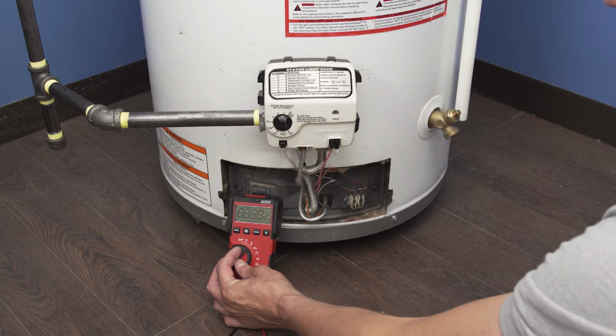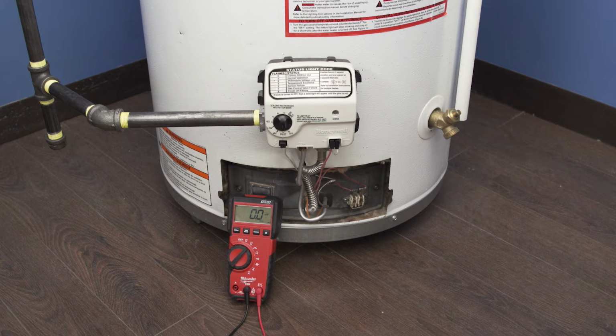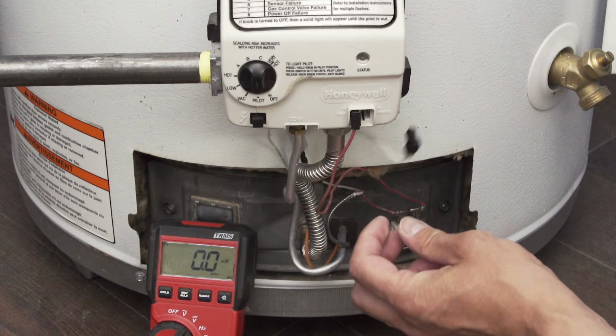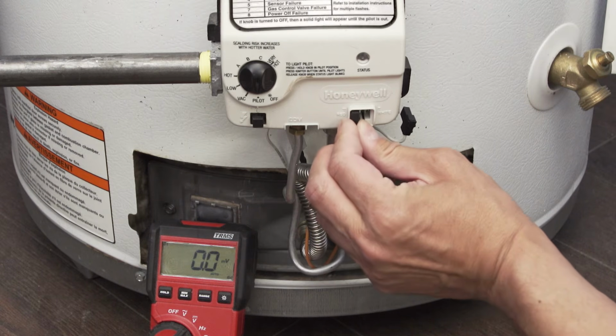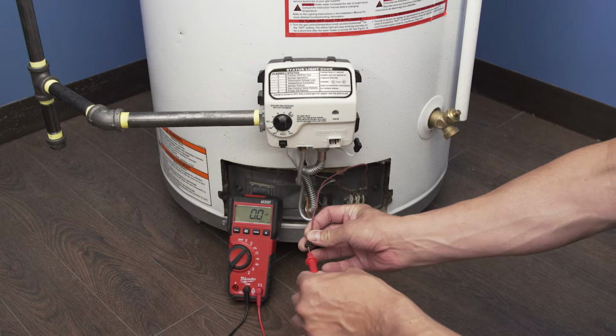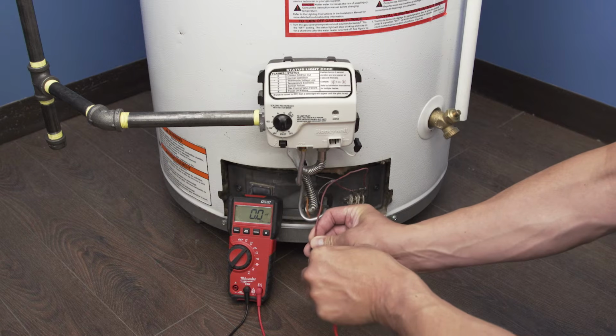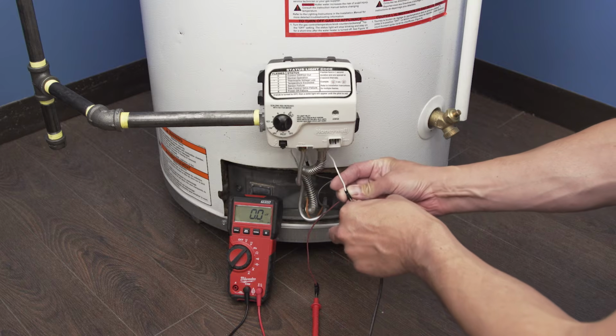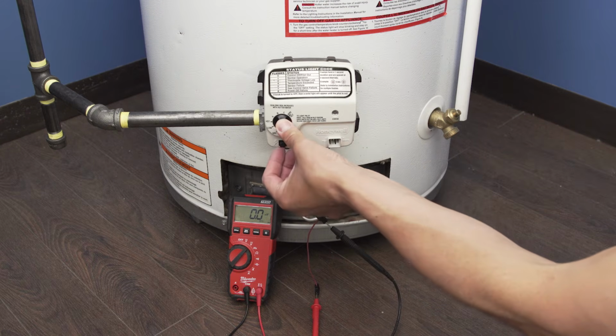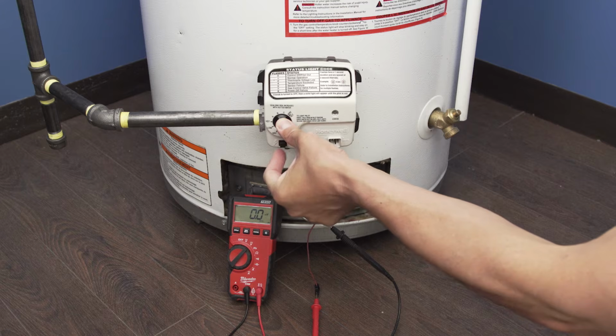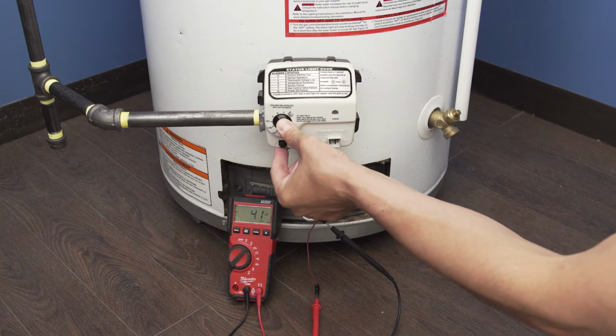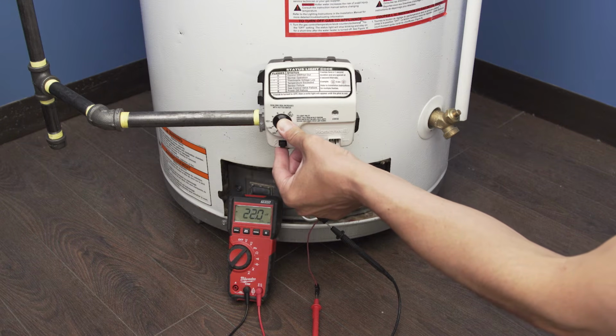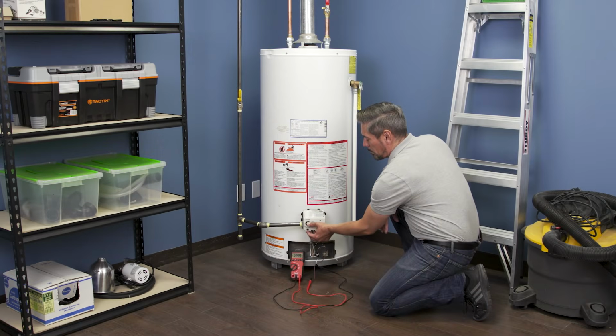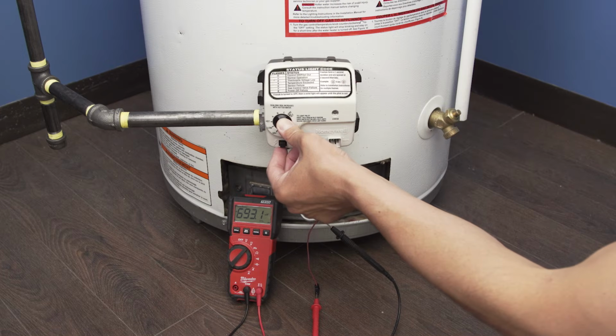First, set the multimeter to the volts DC option. Disconnect the two wires that lead into the control valve. Now connect the probes to each connector. Relight the pilot and hold down the button. The voltage should start to rise over the next few minutes as the thermopile heats up. In an open circuit test, a healthy thermopile should read between 650 and 850 millivolts.